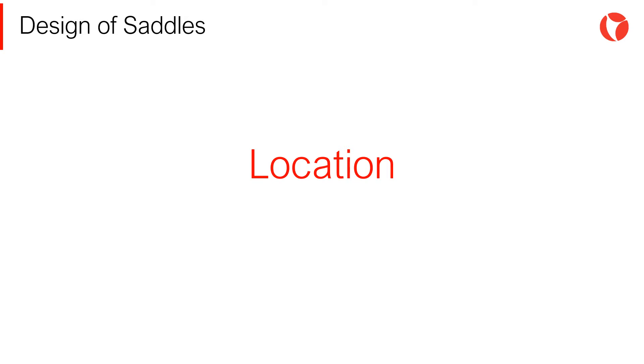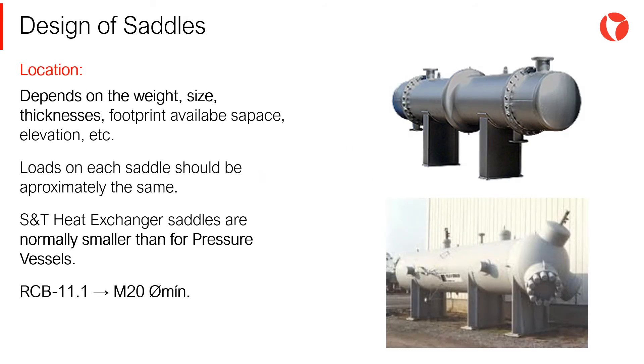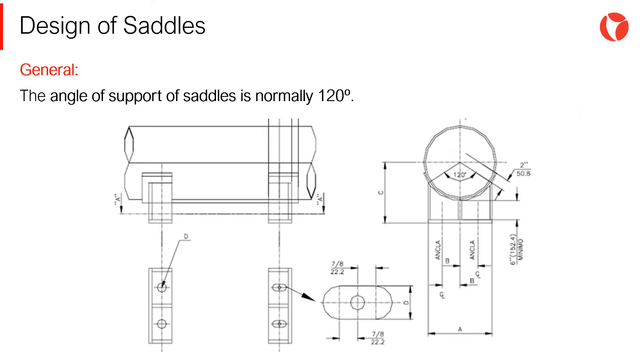The location of the saddles is a fundamental aspect of the design process for this type of equipment. There are numerous publications and recommendations about the location of the saddles. It is advisable to start the design of the heat exchanger supported by means of two saddles, placed in such a way that the loads on each of them are approximately the same. The support angle of the saddle used to support the shell and tube heat exchanger is normally 120 degrees.